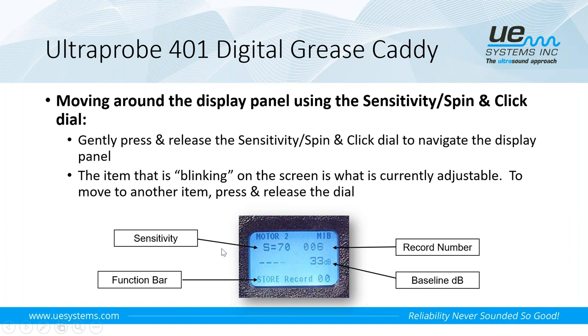In this case, in the middle here, we see some little dashes, and there would be an arrow pointing to the right. When you see the arrow pointing to the right, it's telling you that it's not picking up anything. It's telling you to turn up the sensitivity. If we were to make contact with a bearing here, more than likely the arrow would go away and we would see a decibel level number here in the middle. So where these blinking dashes and this arrow are, once we have the instrument in range, or once we're making contact with something, we'll see that arrow go away and we'll get a decibel level reading here.